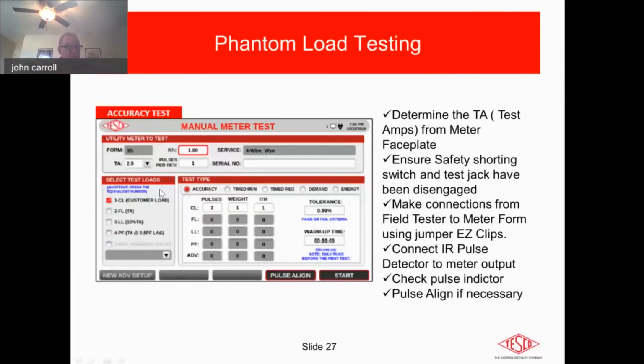This is the same screen we saw before. The only difference is you'd have full load, light load, and power factor selected. You choose what you want. And I would say, for the most part, you'd be looking at a full load, maybe 4 or 5 pulses, perhaps. Light load, because the light load is now 10% of the 2.5 amps. It's a very low condition. You may only want 1, 2, possibly 3.